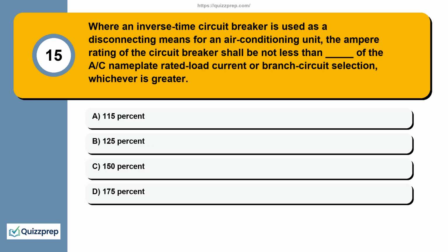Question 15. Where an inverse time circuit breaker is used as a disconnecting means for an air conditioning unit, the ampere rating of the circuit breaker shall be not less than __________ of the AC nameplate rated load current or branch circuit selection current, whichever is greater. 115%, 125%, 150%, 175%.